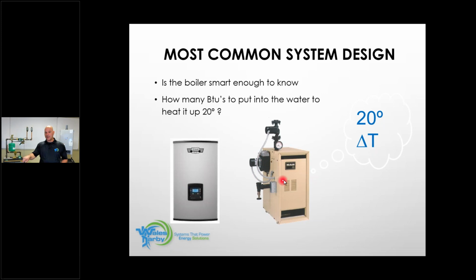We're going to go into this cast iron heat exchanger. Underneath here is where the burner is. The flames are going. The water's coming in. It's circulating across those cast iron sections. It's heating up, and then it's coming back out 20 degrees hotter, I'm sorry. And that is all done by design through the size of the circulator, the size of the piping, and the capability of the boiler, the BTU of the boiler. We're exchanging the energy that the flame source is making up through the cast iron sections. We have our flue passageways, and then we have the waterways on the other side of the flue passageways. We're exchanging that energy back into the water, sending it back out to the house to heat the home.